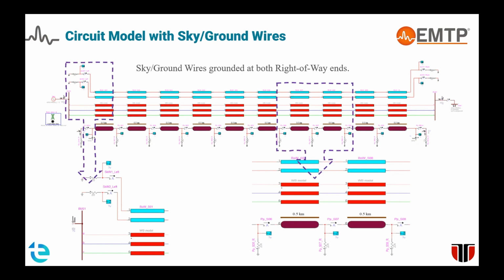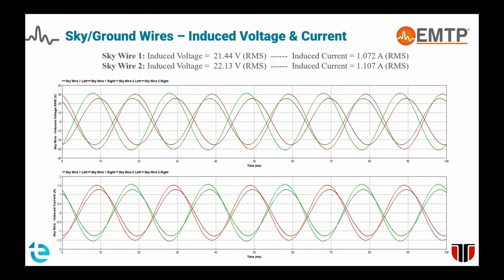Using EMTP-RV, we simulated and first present the induced voltage and currents in the sky wires. They are also metallic structures, so the electromagnetic field created by the power line phase conductors affects them too. In this case we have both inductive coupling and capacitive coupling. The sky wires are above ground, so they are not protected from the electric field at the surface of the earth. We have induced voltages and currents.